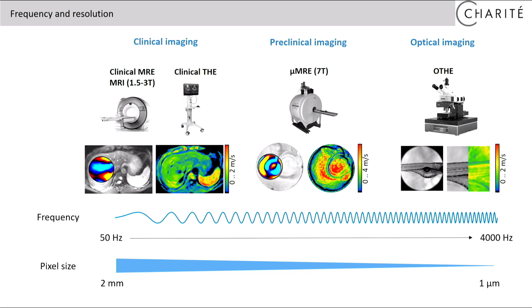Well, these are the modalities for this time harmonic elastography. As you see here, the pixel size in the image varies from 2 millimeter, which is a standard pixel size in clinical MRI. I must say it's not only MRI of the liver. So therefore, these images are almost empty, right? If you have such big pixels, it's like a staircase more than a well-resolved image, right? Nevertheless, images look like this, and here you see in the color contrast stiffness. So greenish colors indicate soft tissue, reddish colors are more stiff tissue here.